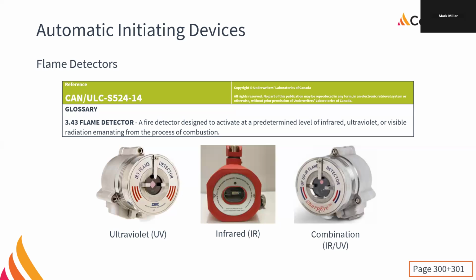Flame is bad in somewhere like an aircraft hangar or a flammable oil testing laboratory. So we use flame detectors. It's great because it provides large open area protection. You can't put a pile of smoke detectors or heat detectors on the roof of an aircraft hangar. It's not going to work right, especially since the one wall is all door. So anything that's relying on airflow is going to cause issues, and we want to detect it as quickly as possible. Again, the sheer cost of the equipment in there, and the fact that these aircraft are coming in, they're not empty of fuel. And if you have a large amount of jet fuel, that can be an issue.